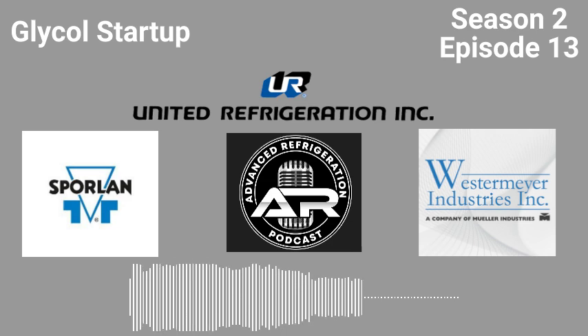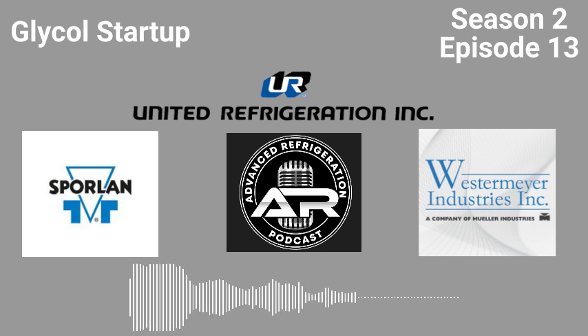35% is a -6, and then it bursts. They have a freeze point, and they have a burst point. So there's, I think it's negative... It's like 10 degrees, 15 degrees colder than the freeze point is the burst point. I'd be absolutely lying if I told you yay or nay. I have no idea. I know what the freeze point is. I just don't know what the burst point is. Off the top of my head, if I had to take a guess, I think it's -24.